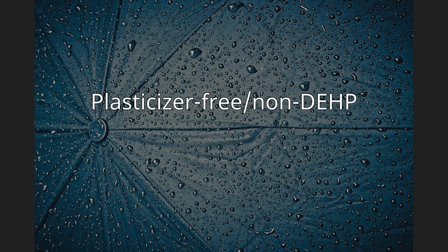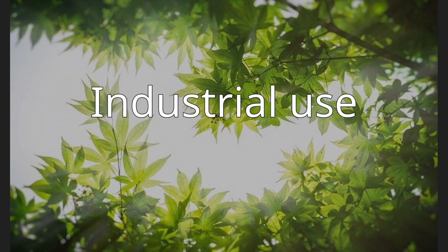Plasticizer-free/non-DEHP. Tygon tubing is available in plasticizer-free/non-DEHP non-phthalate formulations. These formulations have a high degree of chemical resistance and do not release any hazardous material when properly incinerated. Tygon 2275 high purity tubing, Tygon ultra chemical resistant tubing 2075, and Tygon plasticizer-free tubing 2001 are all plasticizer-free. Tygon Medical 100 series products are non-DEHP and use a non-phthalate plasticizer. Tygon silver tubing has a plasticizer-free inner bore and a silver-based compound on the inner surface to decrease bacterial growth and protect against microbes.